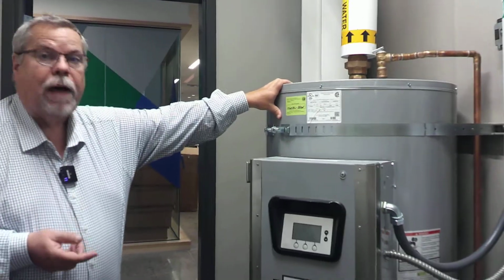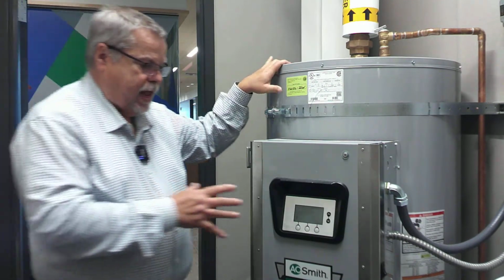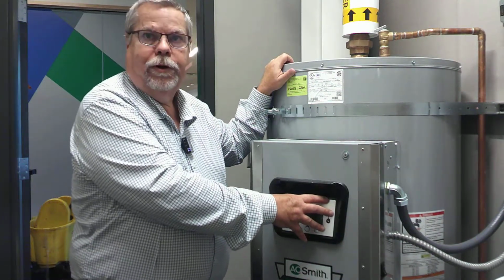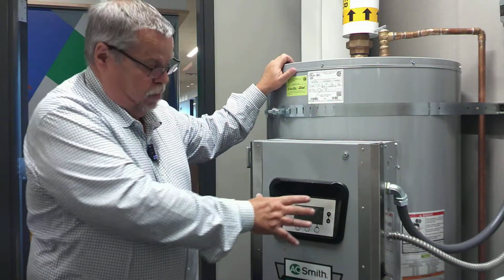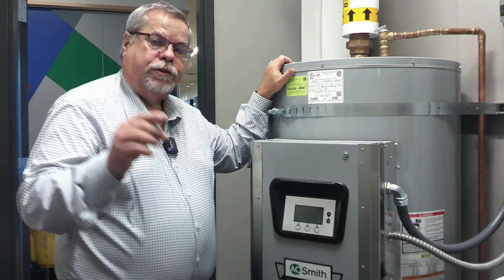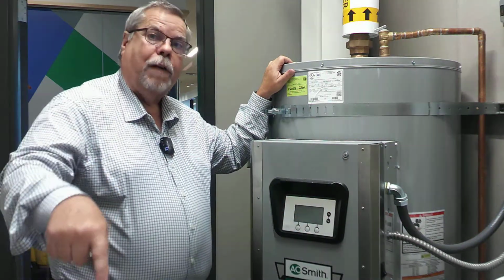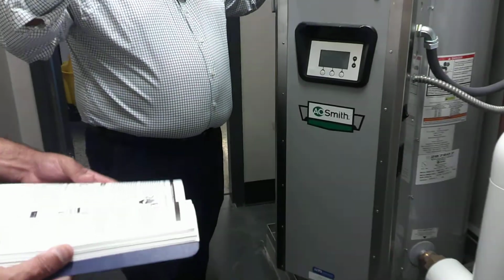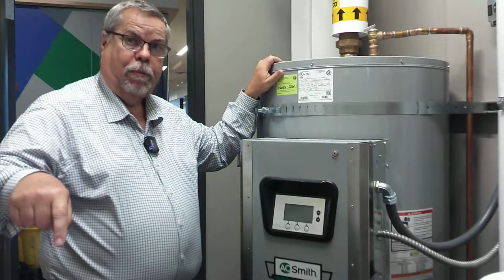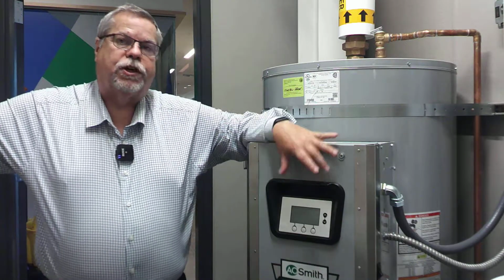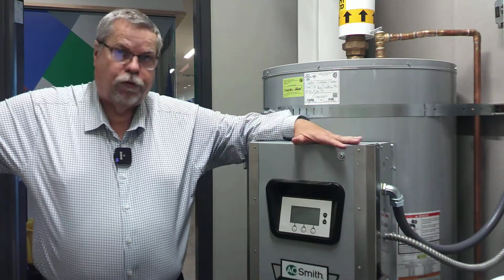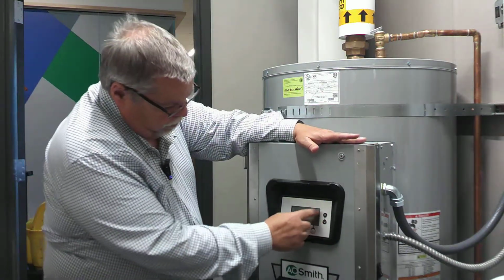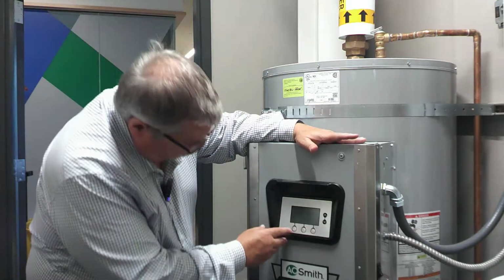This is our top of the line electric water heater, and what that means is it has a very sophisticated control for a water heater. Most of the maintenance guys here aren't used to having controls, but you can do a lot of things with this control. There's a complete breakdown on how to operate this control in this manual, as well as any error codes that might pop up. These controls have a memory. So this not only tracks the current state of the heater, and it has no faults right now, it also records some history, so you can tell how long it's operated, how many cycles it's gone through. It's pretty simple. It's in English, or you can change it to French if you want to.